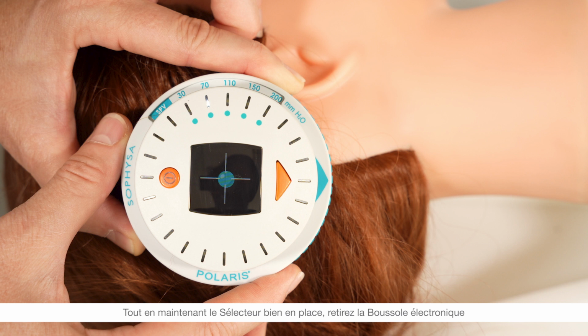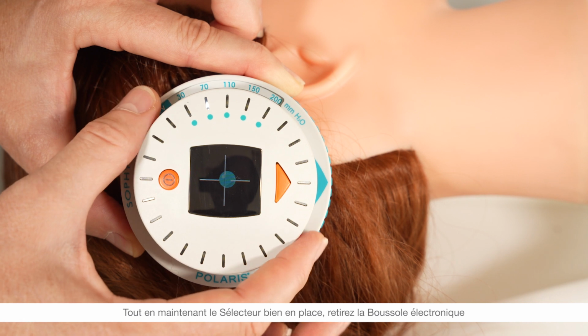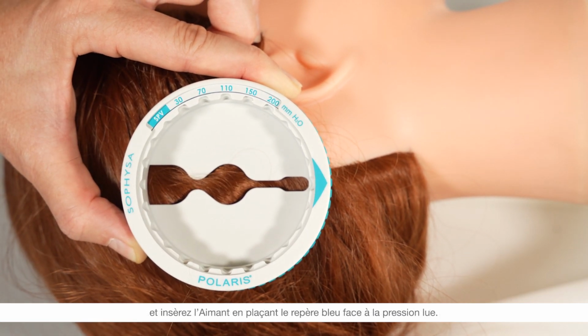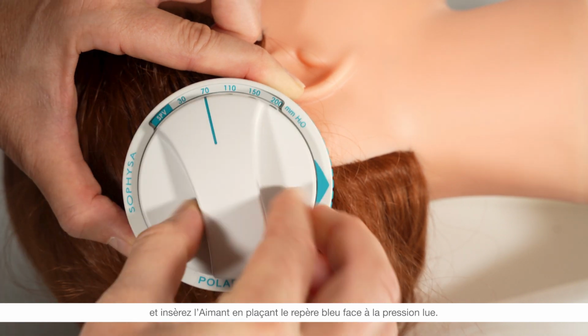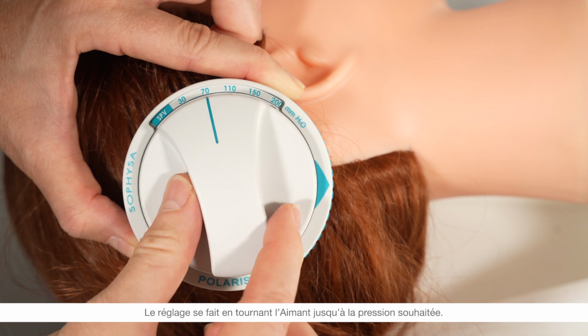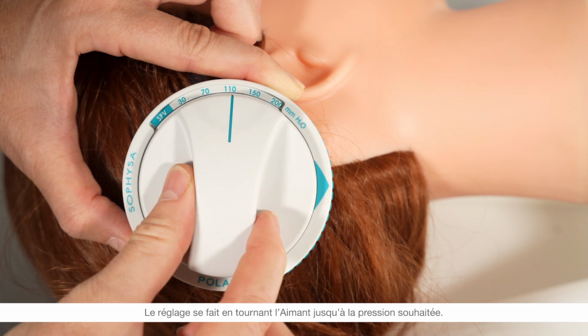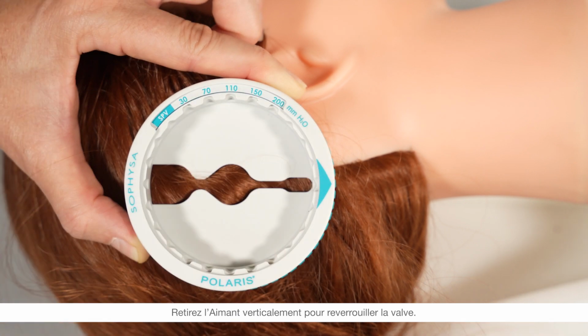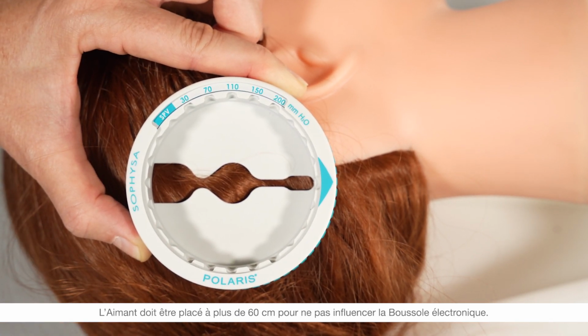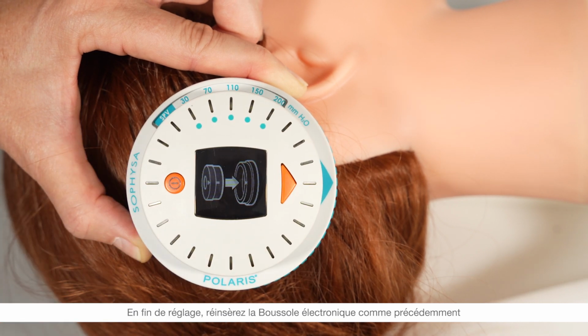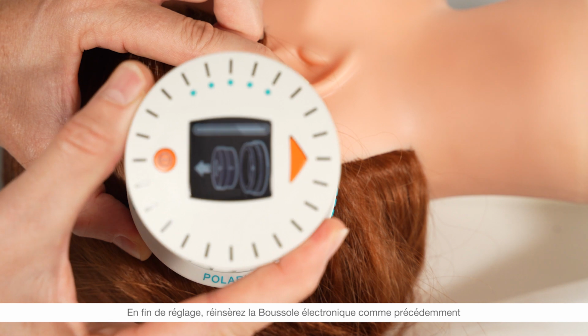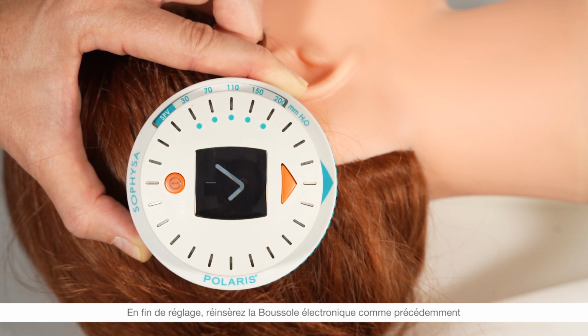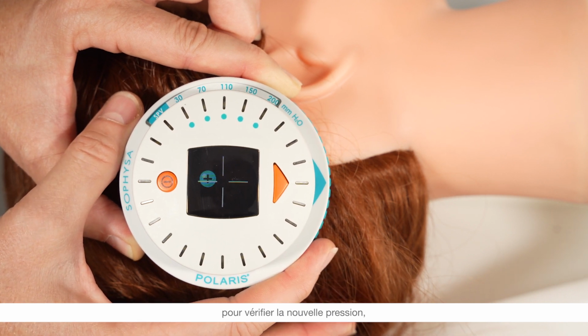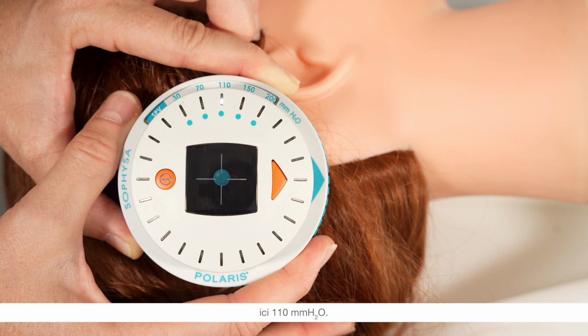Next, while keeping the locator in its centered position, remove the compass and replace it with the magnet, inserting the magnet with the blue mark aligned with the current pressure setting. To adjust the valve setting, rotate the magnet until the blue mark aligns with the desired new setting. Remove the magnet and place it at least 60 centimeters away from the implantation site. Finally, confirm the new pressure setting by reinserting the compass into the locator and check that the arrow on the compass is pointing to the desired setting. In this example, the valve is set at 110 mm of water.